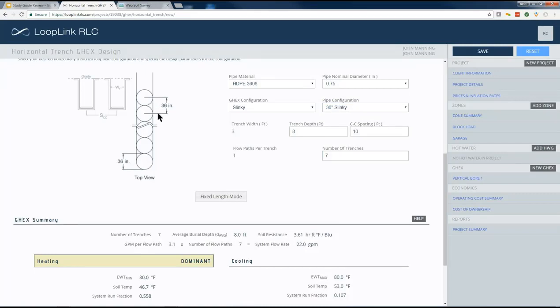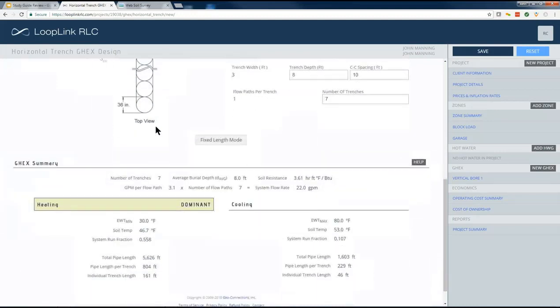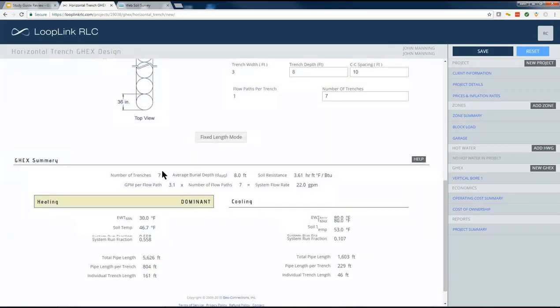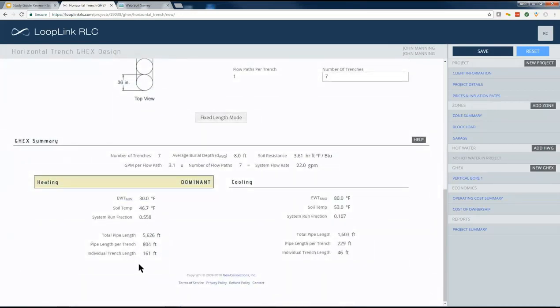So by spreading them out this way, you can see what happens. As you would expect, our trench lengths go up a little bit, and they did. They went up from 155 to about 160 feet per trench. But take a look at what happened to our individual coil lengths. They dropped from 1,200 down to 800 feet. And again, you want to shoot for 800 feet or less on your individual coil lengths here.